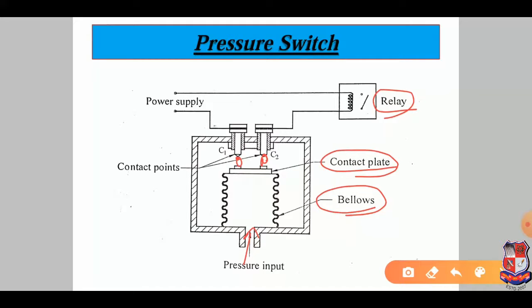Now the preset pressure can be changed by modification of pressure switch. It is adjustable and most pressure switches contain two sets of contact, one normally open and other normally closed. The contact in a normally open switch remains open until the pressure rises above the set pressure. The contacts in a normally closed switch remain closed until the pressure rises above set pressure.